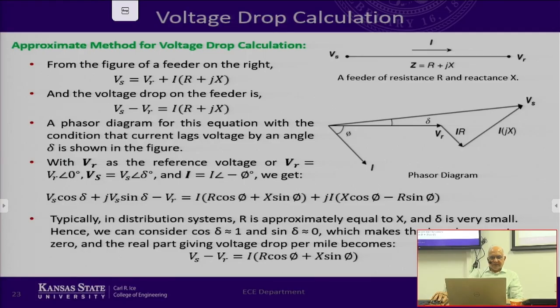And then once we do that, we can see that the approximate voltage difference between Vs and Vr is equal to I times (R cosine phi plus X sine phi). Very simple calculation here. Once you know the power factor of the load, which is cosine phi, the resistance, the reactance of the line, and the magnitude of the current, you can calculate the approximate value of voltage drop. A very simple calculation to avoid doing too many of these calculations.